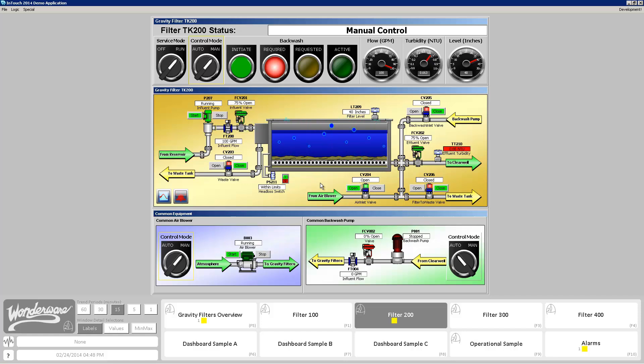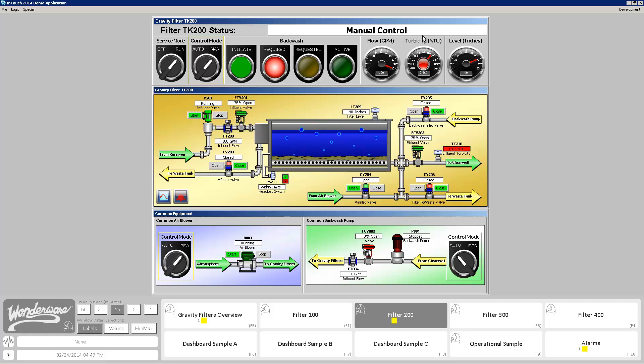Another thing in this demo is what is referred to as a low data-to-ink ratio. There is a lot of ink on the screen that's not actually conveying any information. For example, the 3D pipes with flanges and bolt heads, the 3D chrome trim rings, and the glare effects on the gauges — many of these offer no value and in some cases have detrimental value. They may make the screen more visually interesting, but that can also be distracting and reduce overall situational awareness.